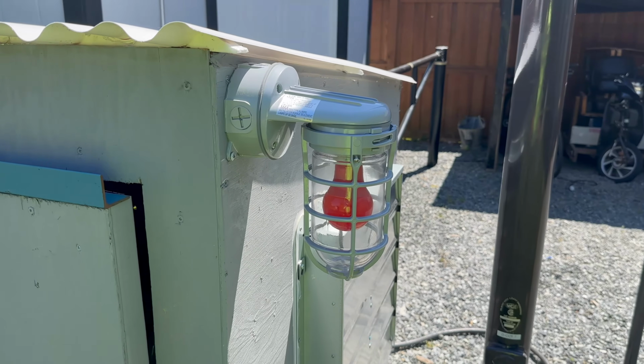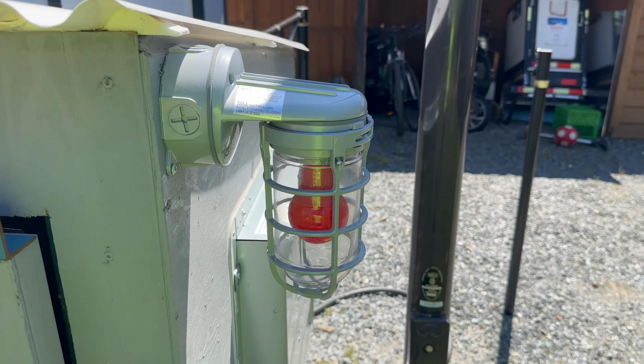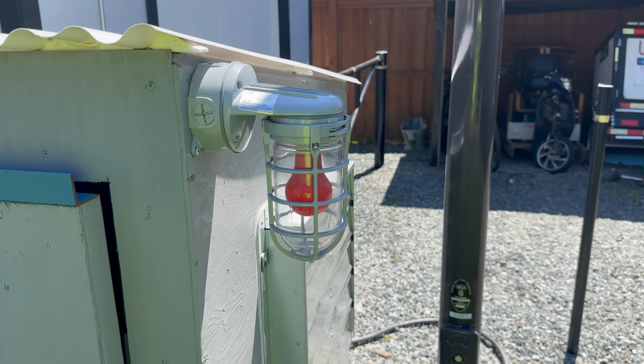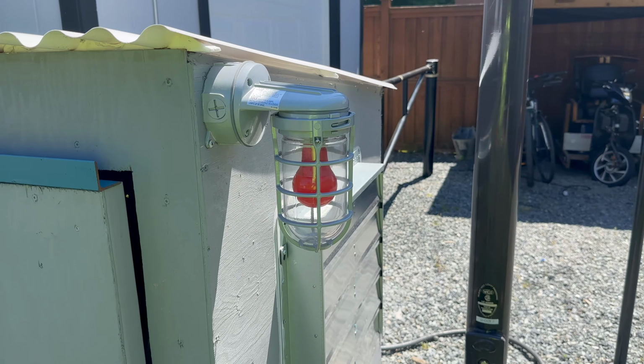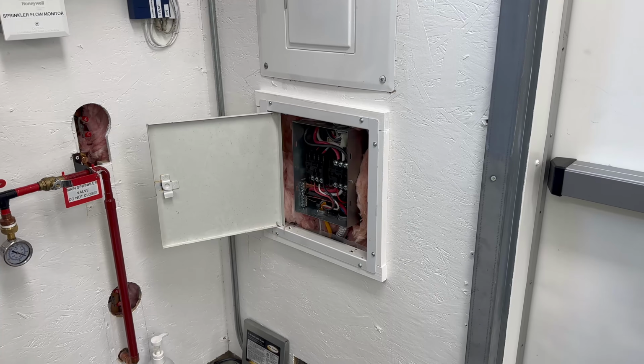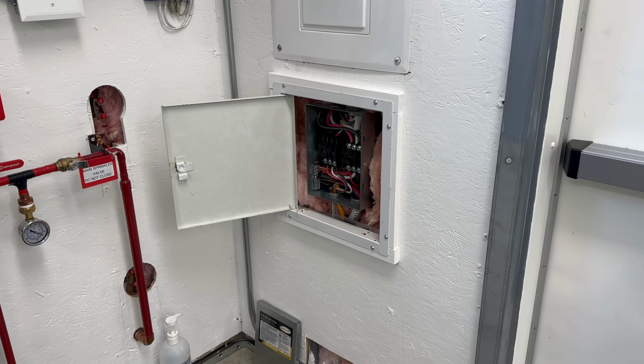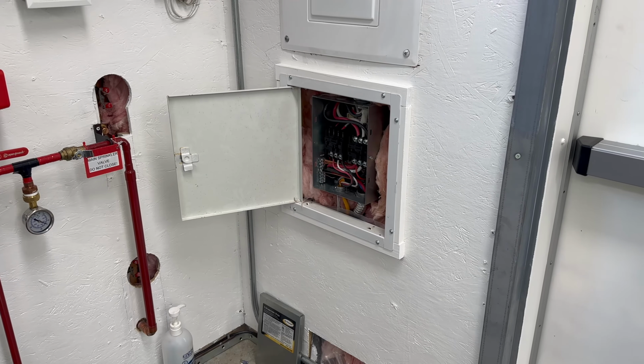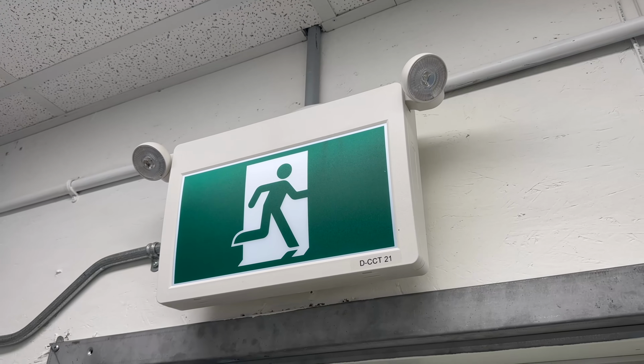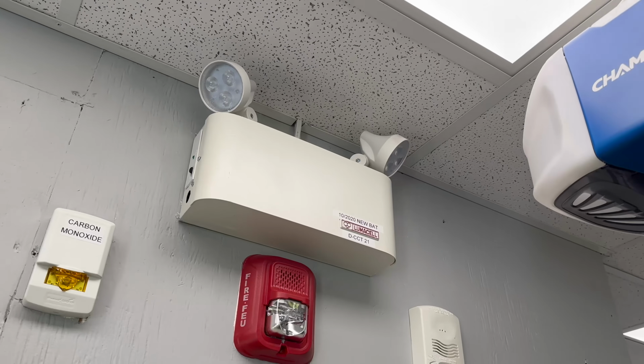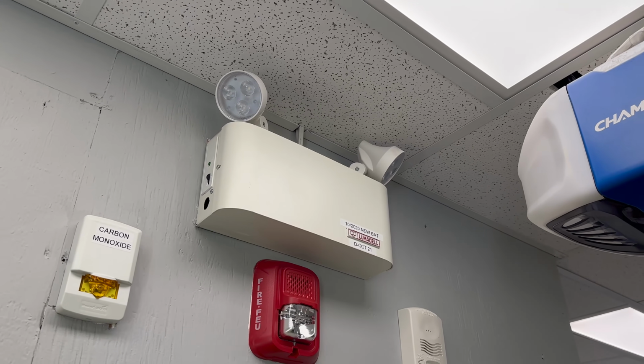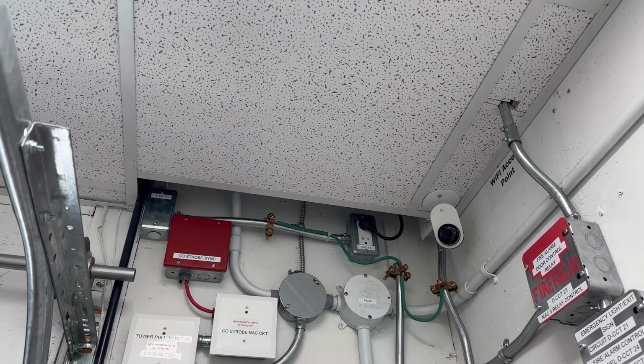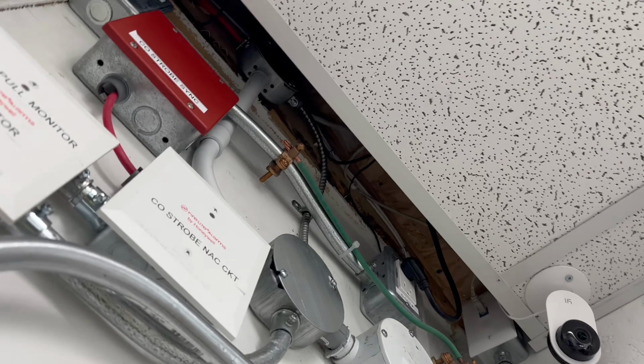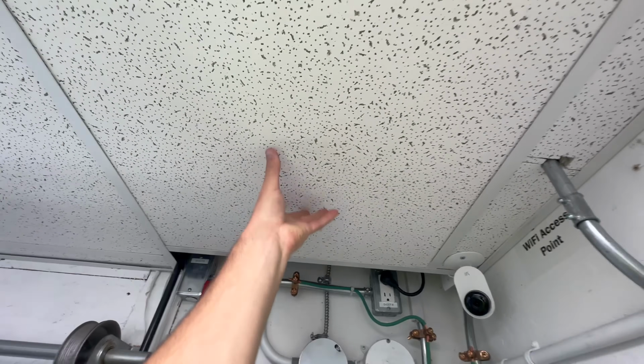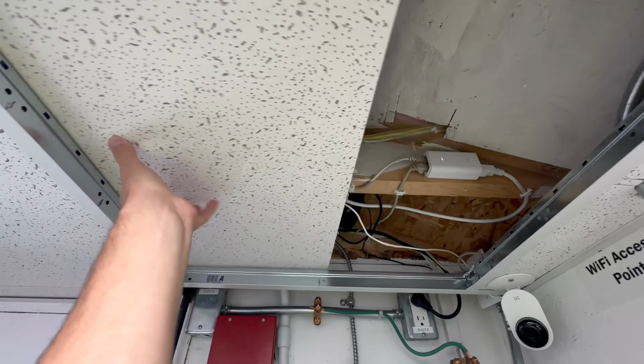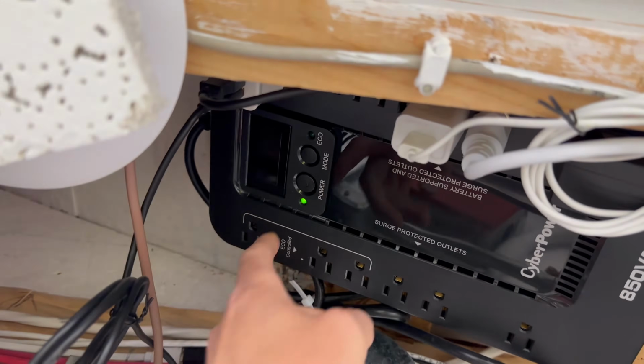Something to look for is this red light mounted on the outside of the generator building, which is tied into the generator's power and will illuminate when the generator is running to show that the generator is supplying power. In 32 seconds, that is the length of time that the power is out, and during that time I do have battery backup systems to cover that time delay. I have battery powered emergency lighting such as this exit sign, as well as multiple of these battery powered emergency lights which come on instantly. I also have UPSs or uninterrupted power supplies that are mounted up in the ceiling. Here is one of them.